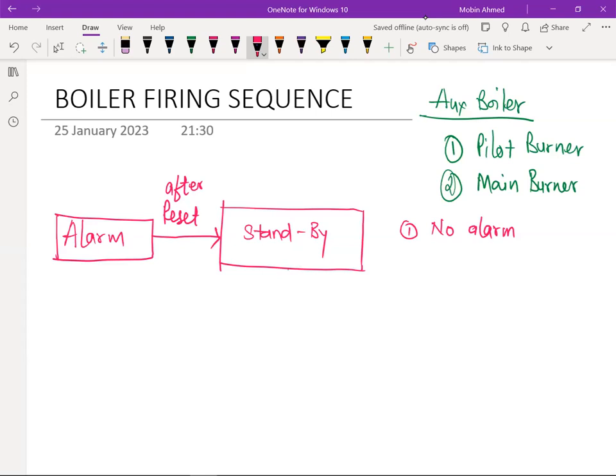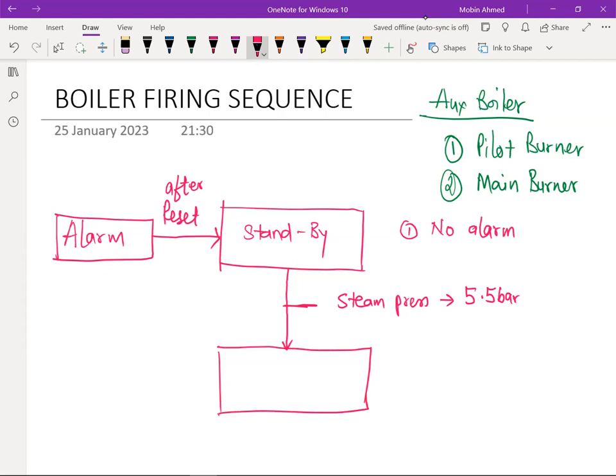Okay. Once it is in standby mode, the firing sequence will start when your steam pressure comes to the start signal, that is the on signal, and suppose that is 5.5 bar. So at 5.5 bar steam pressure, your firing sequence is going to start. And this is the firing sequence. First is the pre-purging. Pre-purging means your FD fan is going to run continuously. FD fan starts and runs.